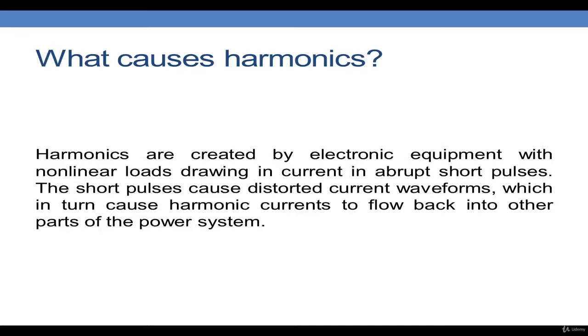Harmonics are mainly created by electronic equipment besides the generator. With nonlinear loads drawing current in abrupt short pulses, those short pulses cause distorted current waveforms, which in turn cause harmonic currents to flow back into other parts of the power system. There are two load classifications: linear loads, where current drawn is proportional to the voltage, such as heaters and motors, and nonlinear loads, where current is disproportionate to the voltage, such as static loads.